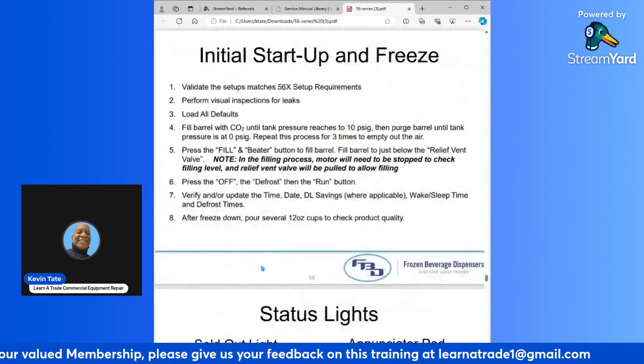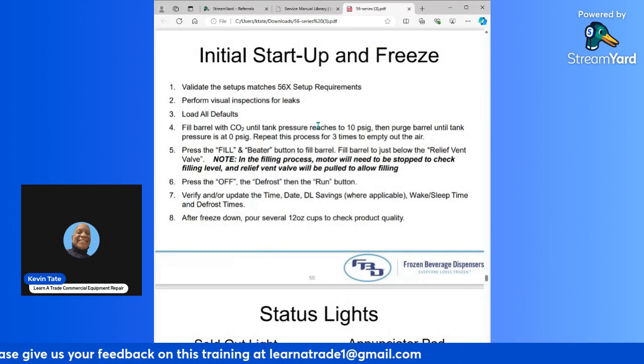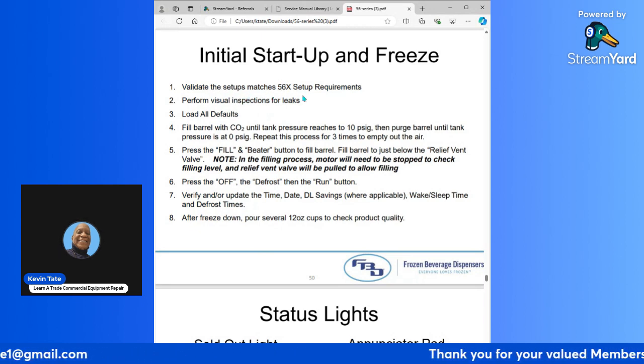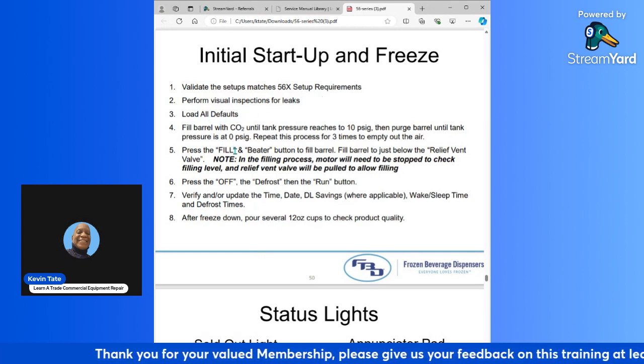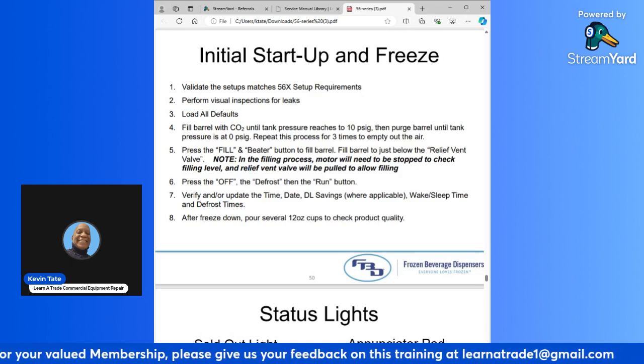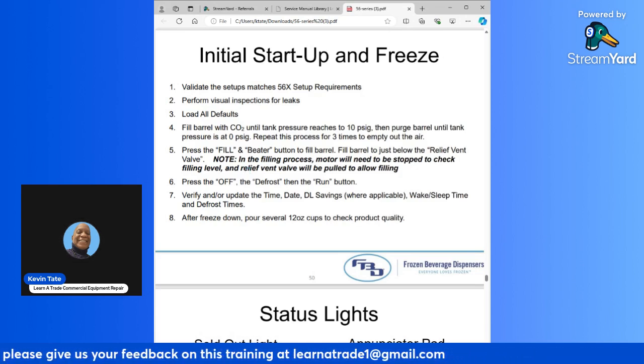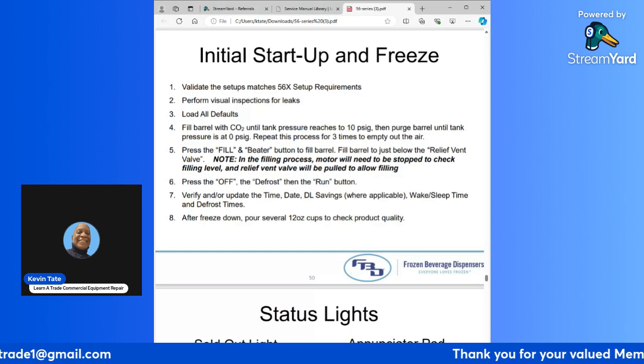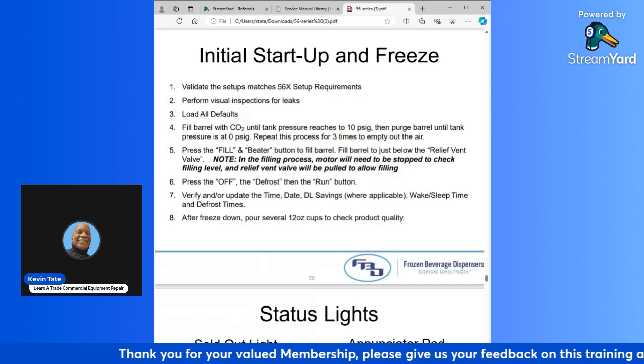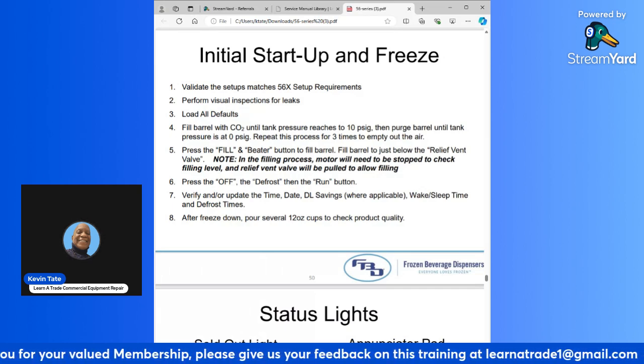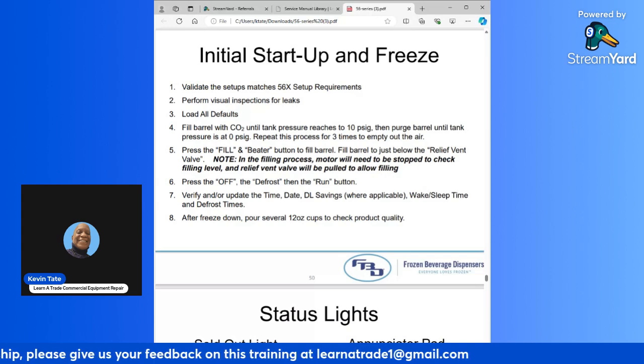Next, we're going to go to initial startup and freeze. Validate the setup matches 56 series setup requirements. Perform visual inspection for leaks. Load all defaults. Fill barrel with CO2 until tank pressure reaches 10 psig. Then purge barrel until tank pressure is at 0 psig. Repeat this process three times to empty out the air.